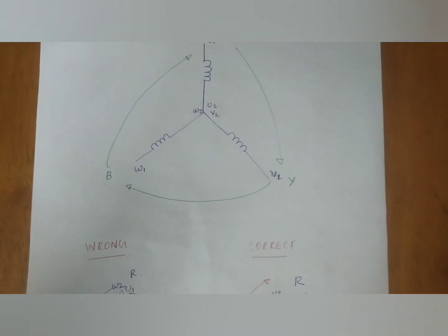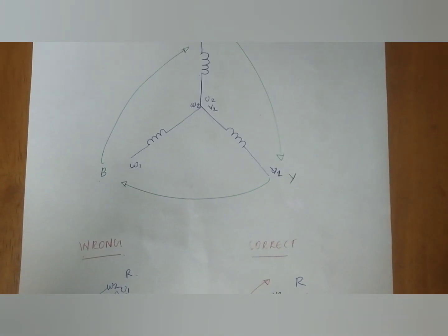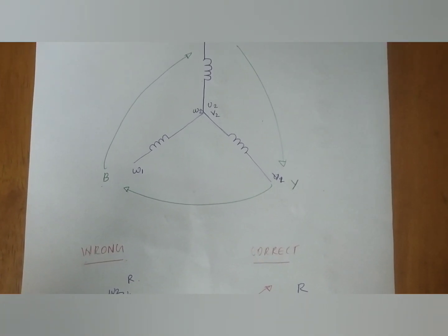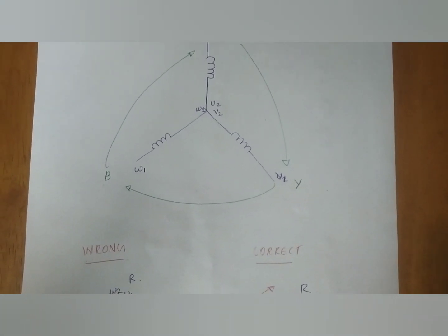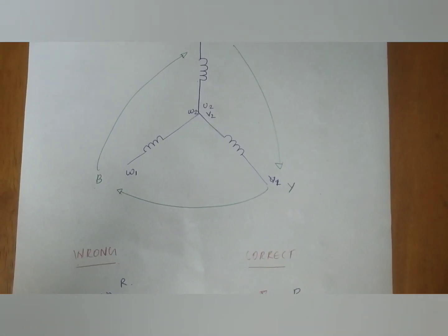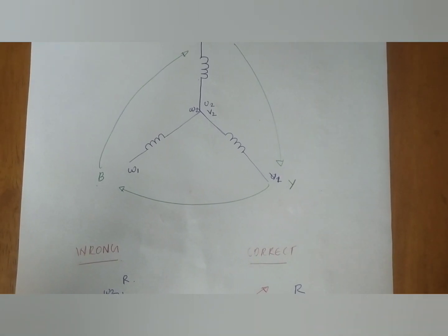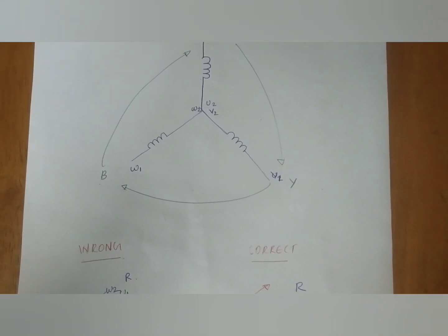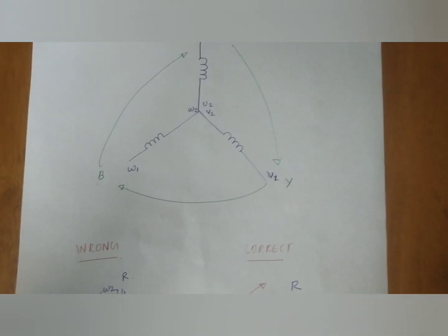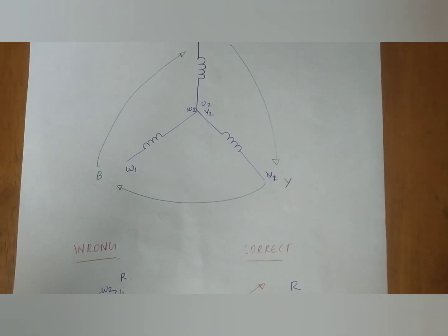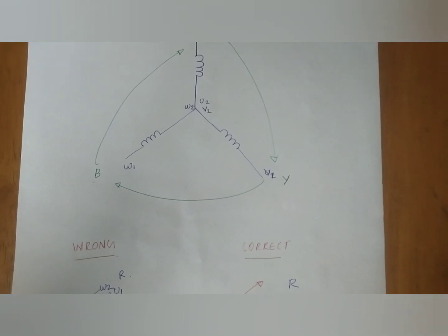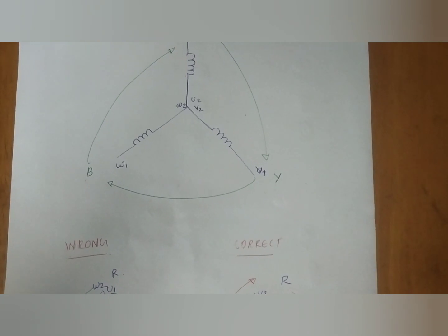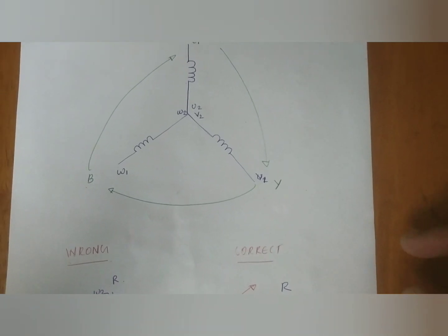What would be the reason? The reason is nothing other than overcurrent. Why is the motor throwing overcurrent? It is because the motor, once it was rotating in clockwise direction, when it is switched on to delta configuration, might have been working in anti-clockwise direction because the phase sequence may not be properly connected. That's why when the motor is turned on to delta, it will try to rotate in anti-clockwise direction and will be drawing large current from the system, which results in the tripping of the contactor.